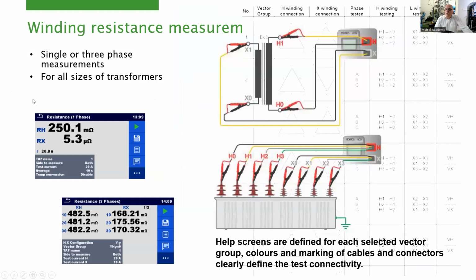How does the measurement itself look? As I said, we can perform resistance measurement of single phase transformers. It's not something special. Or you can perform the measurement on three phase transformers. What does that mean? That means that we connect all 6 or 8 cables at the same time to all the terminals of the transformer.